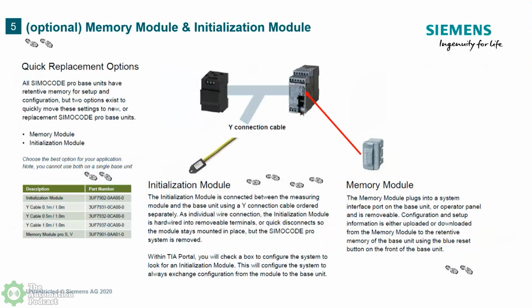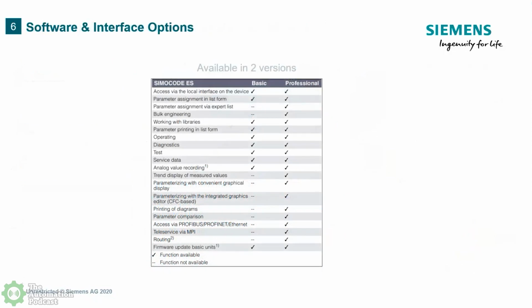The downside of the little memory module is that the SIMOCODE doesn't need it to run. So once they've downloaded it, they could pull it out, put it in their pocket, and walk off. And that's a little bit of the downside, the pros and cons of it. Or you can just leave it in the SIMOCODE and so forth. And then, of course, the third way is using a laptop to program it once it's connected to the communication protocol.